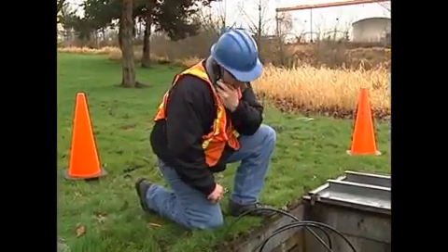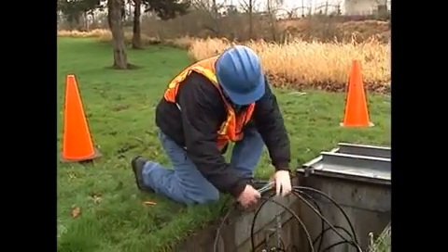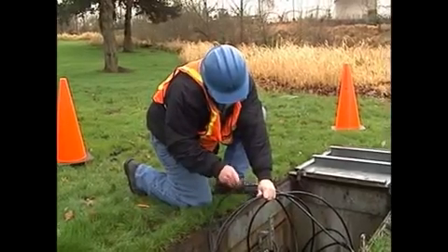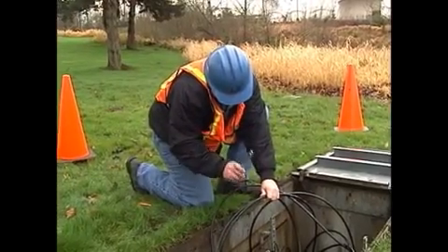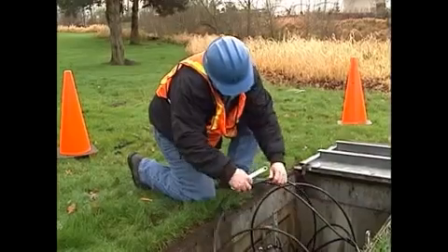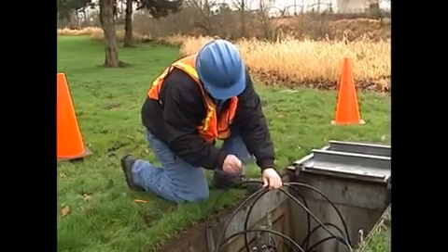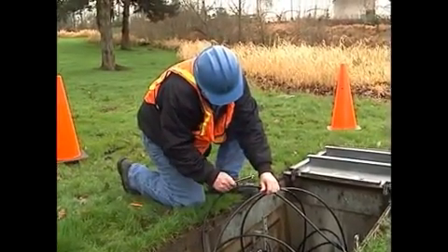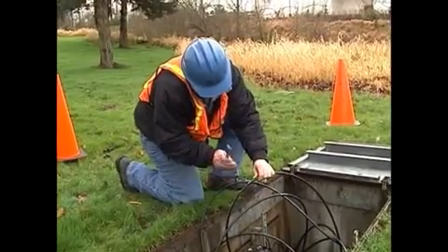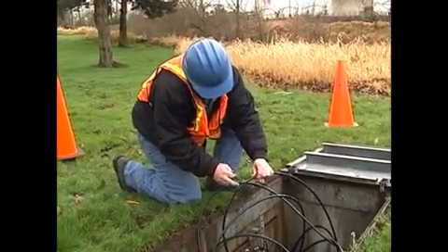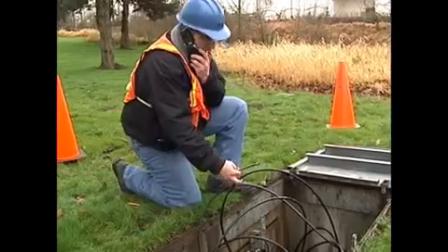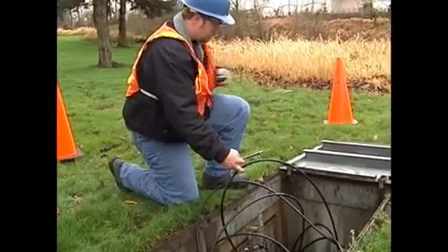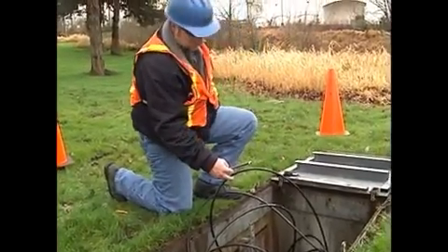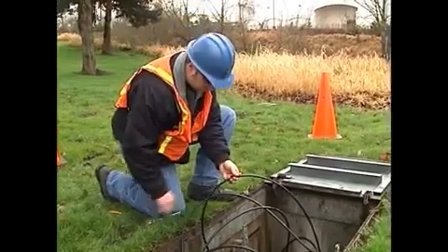Gentle tapping applied to the cable at almost any point along the span can easily be detected by the AFSID as an audible sound as well as a variable LED bar display. The technicians maintain voice contact through the use of cell phones, and to make finding target cables easier and faster, the AFSID is connected to one of the cell phones. This allows the remote technician to hear the output of the instrument while various cables are tested.